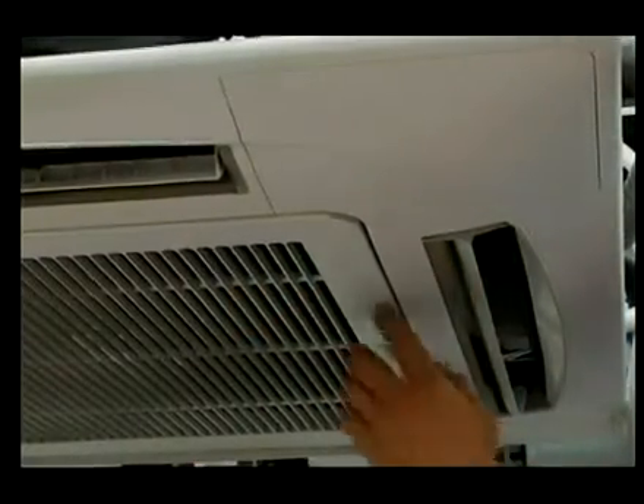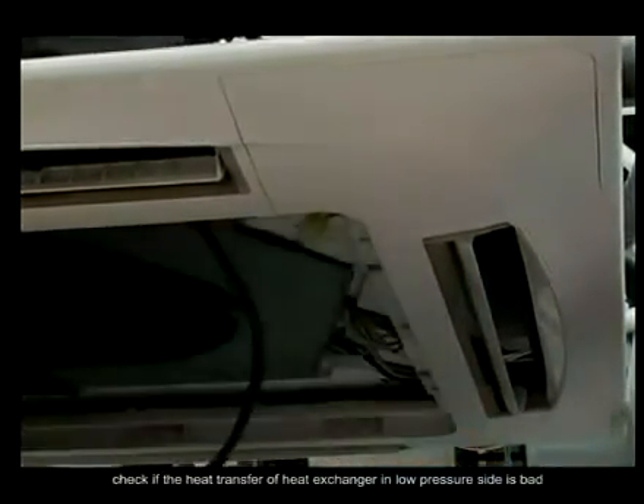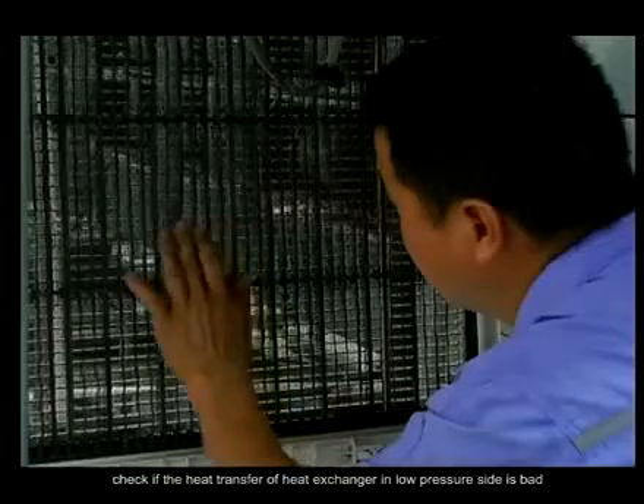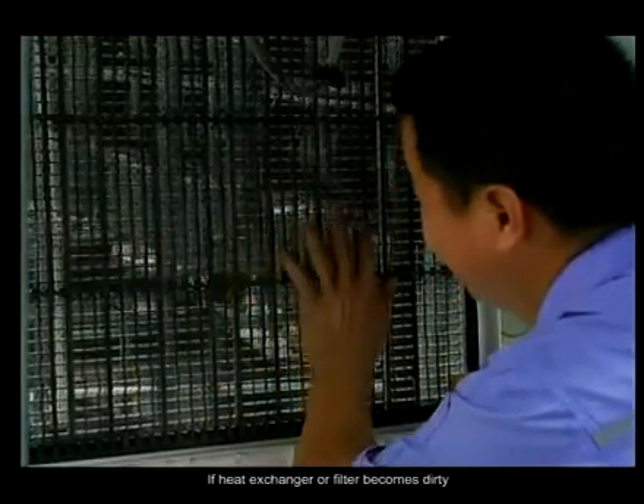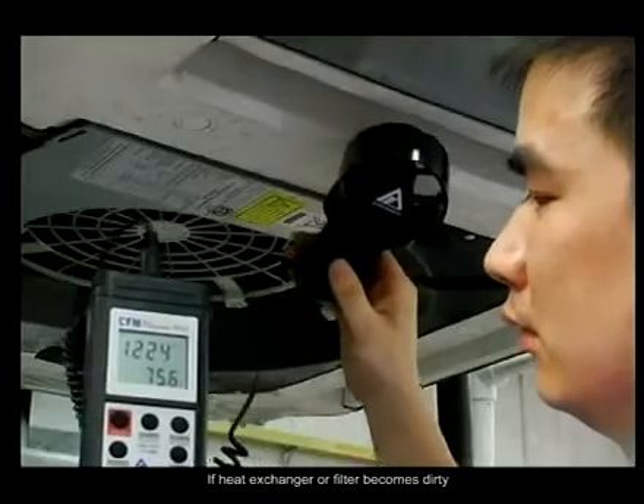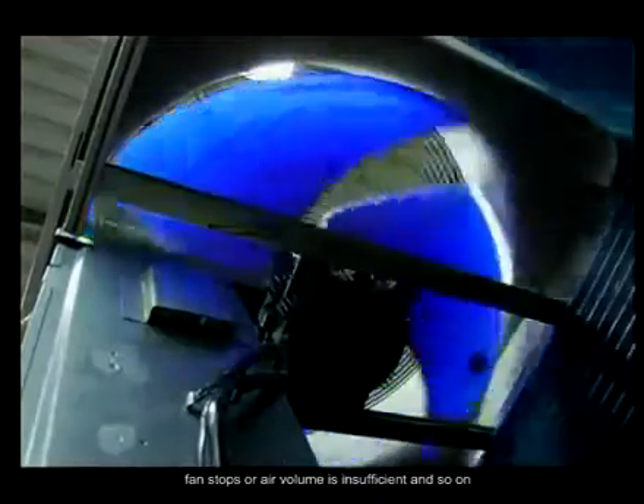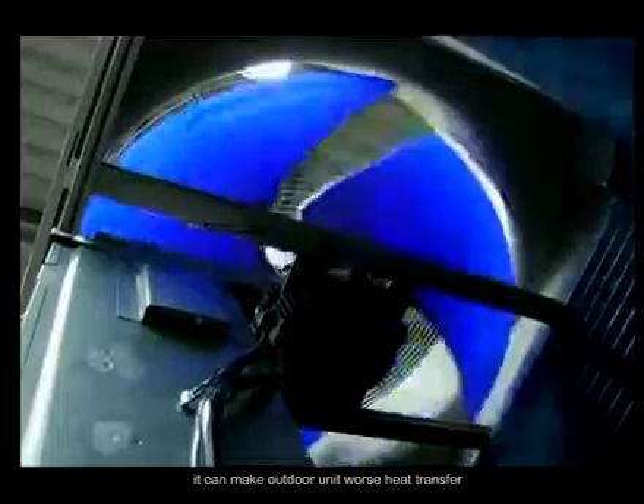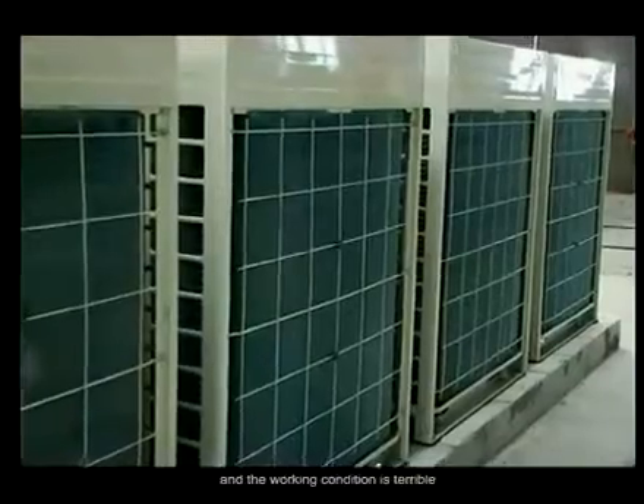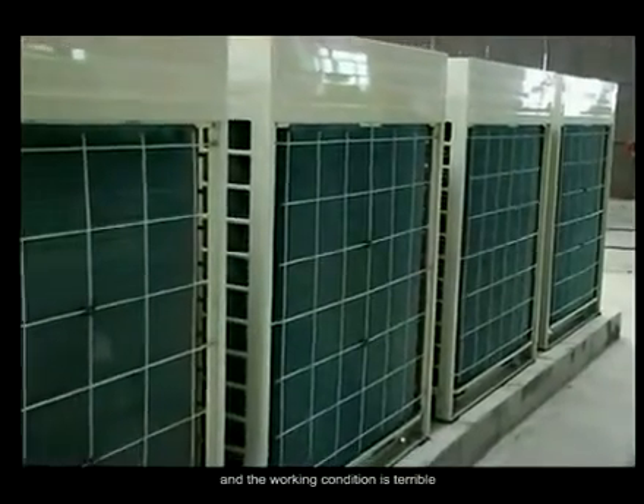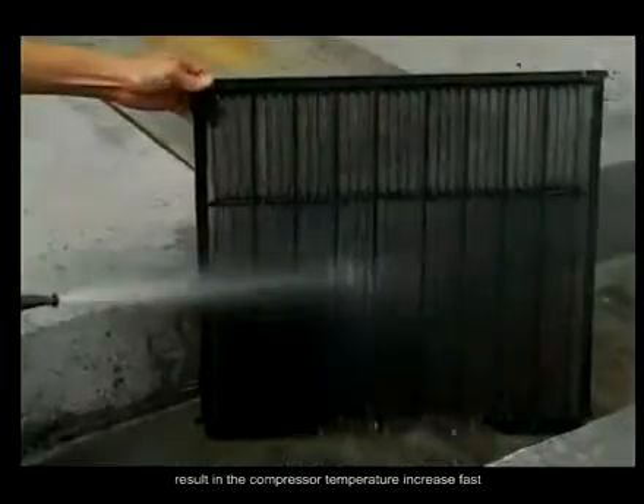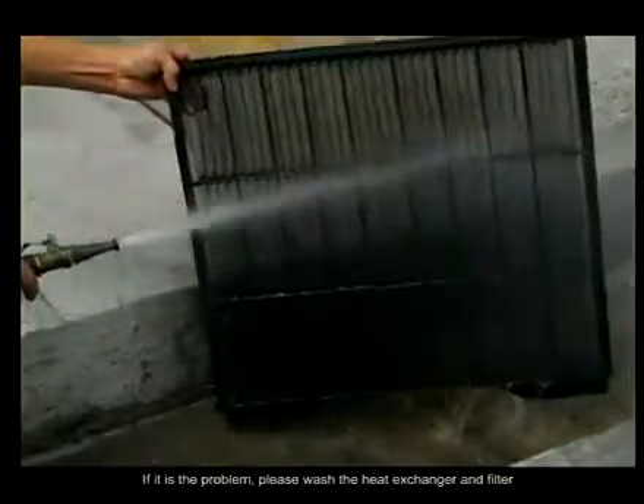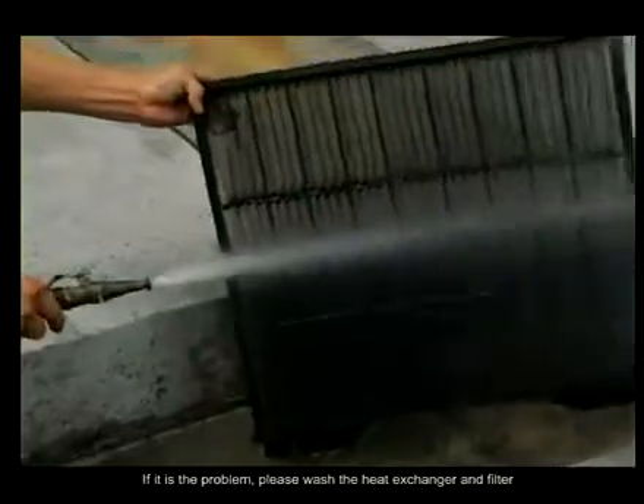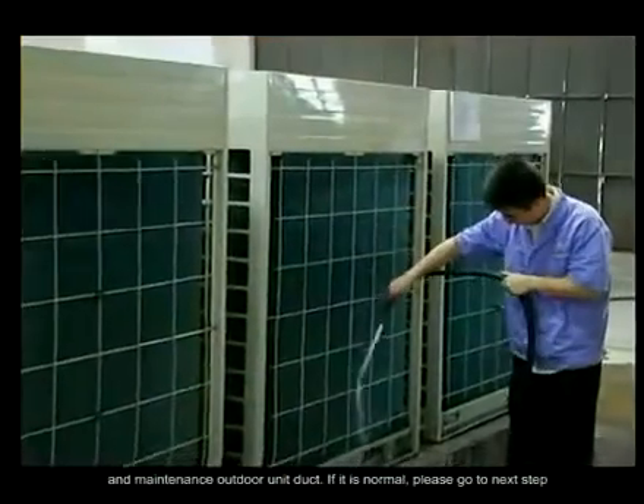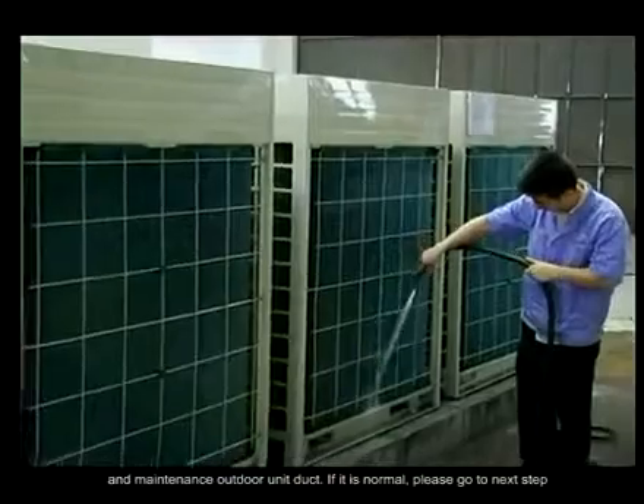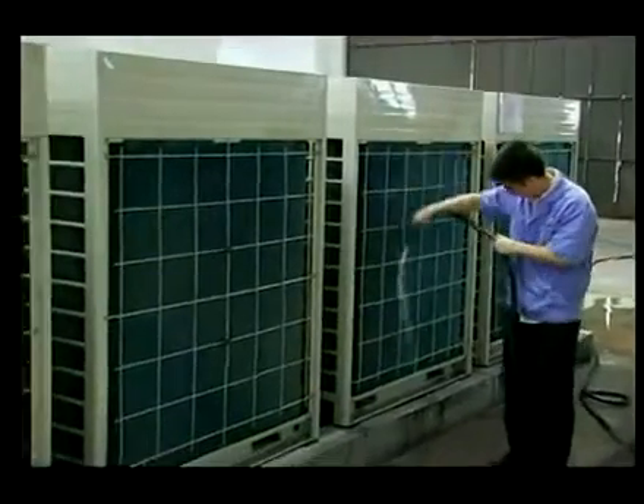Step 3. Check if the heat transfer or heat exchange on the low pressure side is bad. If the heat exchanger or filter becomes dirty, the fan stops, or air volume is insufficient, and so on, it can make the outdoor unit's heat transfer worse, and the working condition is terrible, resulting in the compressor temperature increasing fast. If it is the problem, please wash the heat exchanger and filter, and maintain the outdoor unit duct. If it is normal, please go to the next step.